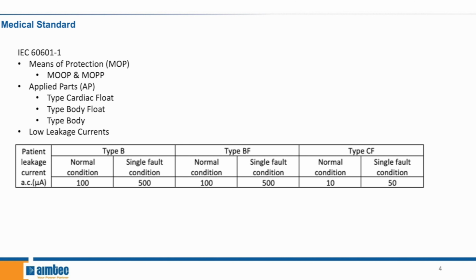Now, this medical standard is IEC 60601-1 and is composed of multiple components, but we'll be focusing only on the following three. The first one is means of protection, or MOP, and this MOP component protects patients and operators from the risk of electrical shocks. There are two types of MOP: means of operator protection, MOOP, and means of patient protection, MOPP.